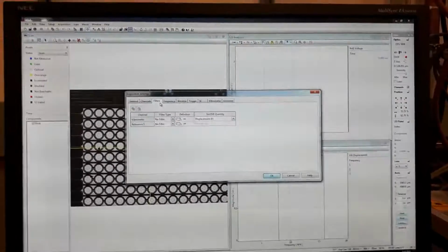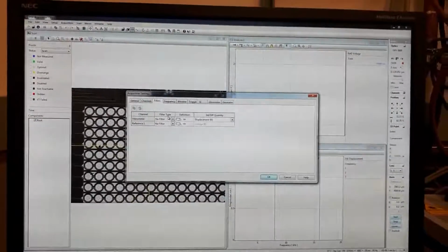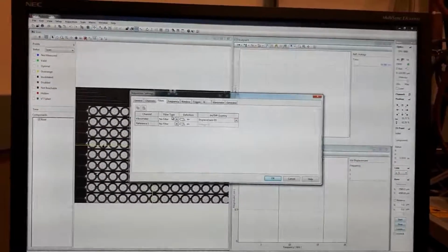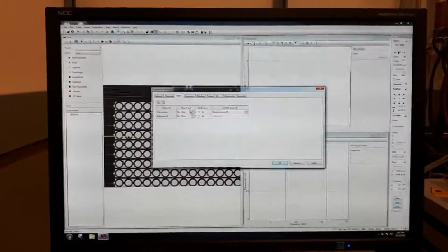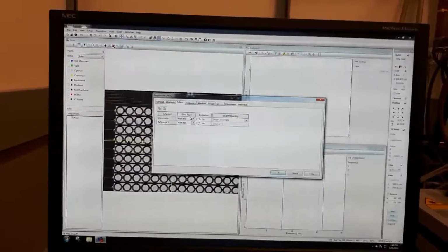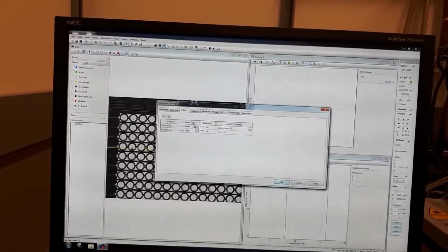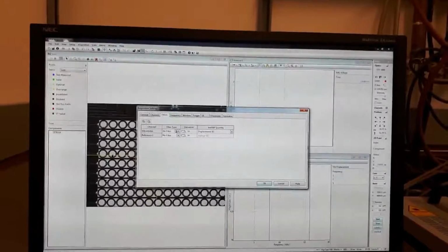For low frequency, I would recommend using the bandpass filter. If you are measuring something in the lower range, and you are getting some mechanical noise from the background, a bandpass filter will work.